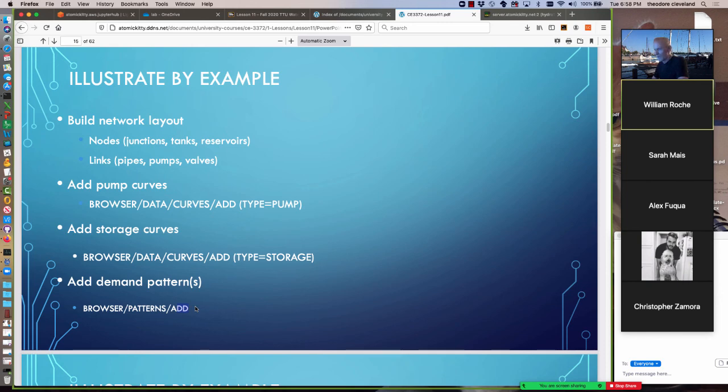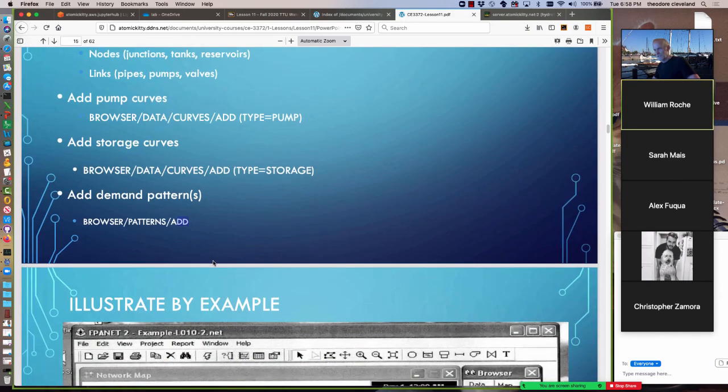And then you can run it with a varying demand pattern to identify if you have hydraulic features that are not sustainable. In other words, tanks drying out or running to negative pressures somewhere. And those 3 are a good starting point that you can adjust as you're adjusting your design and preparing documentation for your client that the design network will satisfy their expectations.